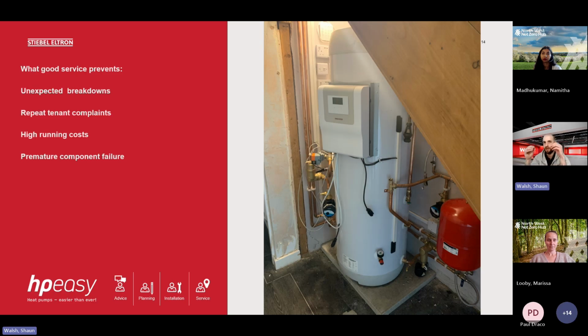As an example, if we have a buffer tank inside the property, so this here is a combined cylinder buffer, our buffer tank here would store maybe 20, 30 degrees of water. We'd pull the water from here and send it outside to the air source heat pump. It warms the evaporator up and stops it from freezing up.